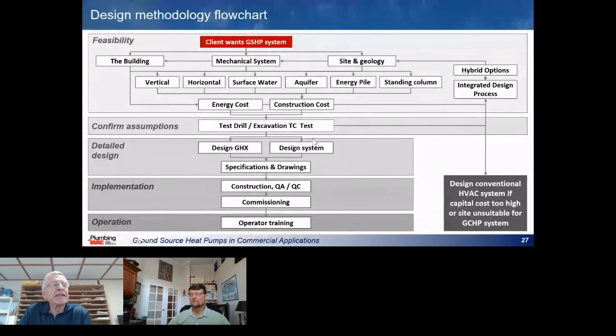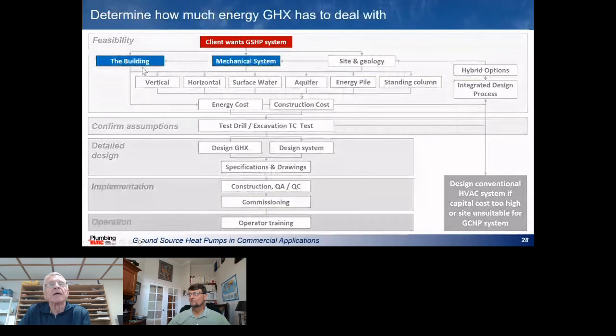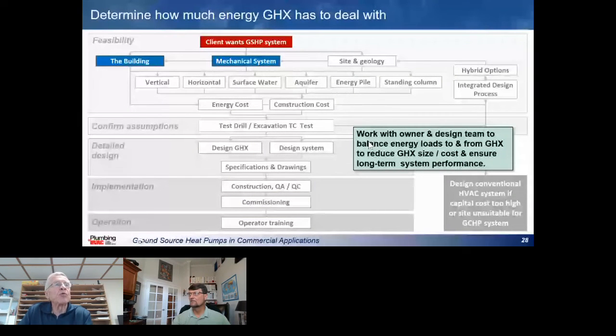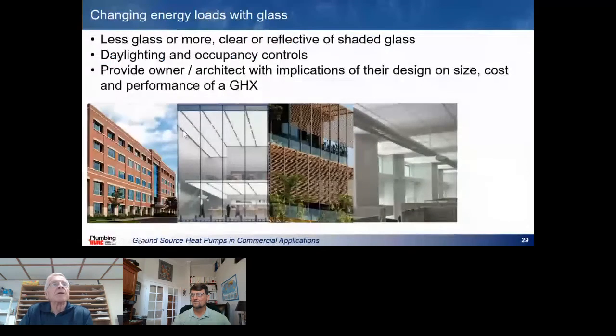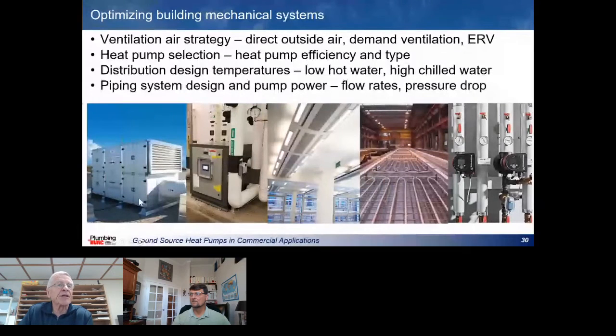So the design methodology really needs to be much different, because you really have to look at, ideally, what you can do with the building by working with the mechanical system designer, with the architect, and with the building owner. What can you do to that building that would make the energy loads that you're going to shove into the ground versus taking out work more efficiently? So a lot of different things: how much glass you're putting on the building, what kind of glass you're putting on the building, how you're shading that glass. Are you taking advantage of the outdoor light to light the building instead of using electric lights to do that? Same thing with a mechanical system, a heat energy recovery ventilation system. You might look at what the efficiency of the boilers are, how you're distributing that heat. If you're looking at 65-degree chilled water through the chilled beams, or 80-degree water through radiant floor systems, and what kind of pumping systems, all of those things have an impact on how much heat you're dumping into the ground versus how much you're taking out.